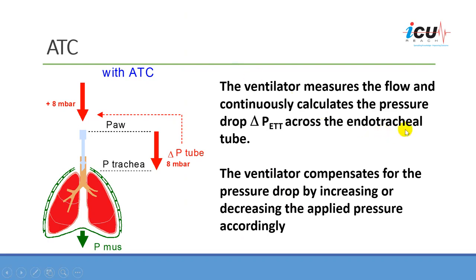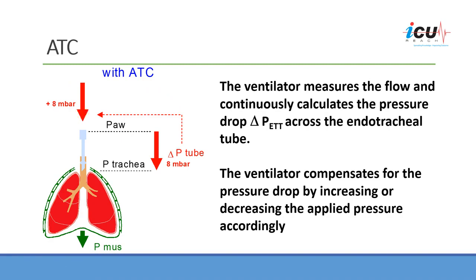The ventilator measures the flow and continuously calculates the pressure drop across the endotracheal tube, then compensates for that pressure drop by increasing or decreasing the applied pressure accordingly. For example, if that pressure drop is 8 centimeters of water between the proximal end and the distal end of the tube, the machine will add 8 centimeters of water as pressure support to overcome the airway resistance.